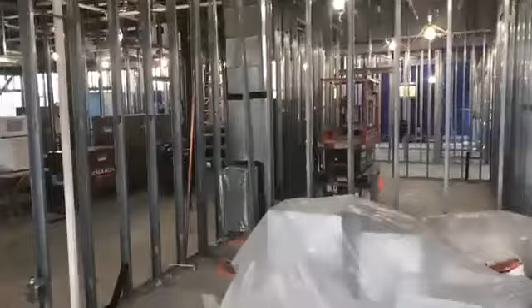The other really critical piece is that there's constantly positive pressure in this room. With that positive pressure differential, nothing infiltrates this extremely sterile environment. We have pressure sensors in certain areas that let anyone entering verify the pressure differential is indeed positive, so that by entering they're not pulling microbes or particulates into the room. There are a lot of unique considerations for healthcare applications, especially a surgery suite, given the requirements for sterility.